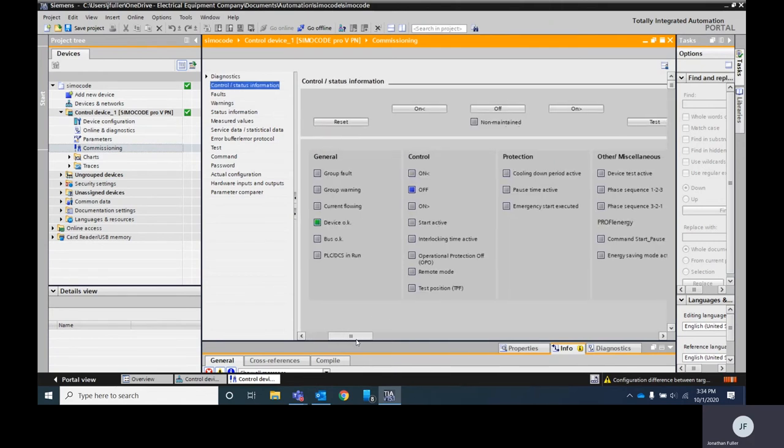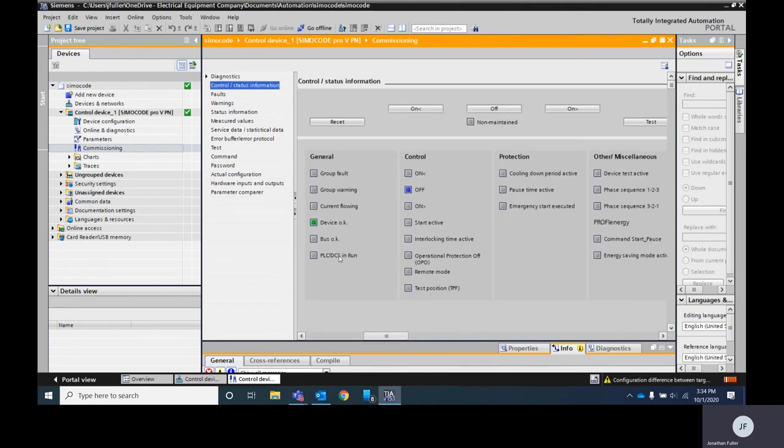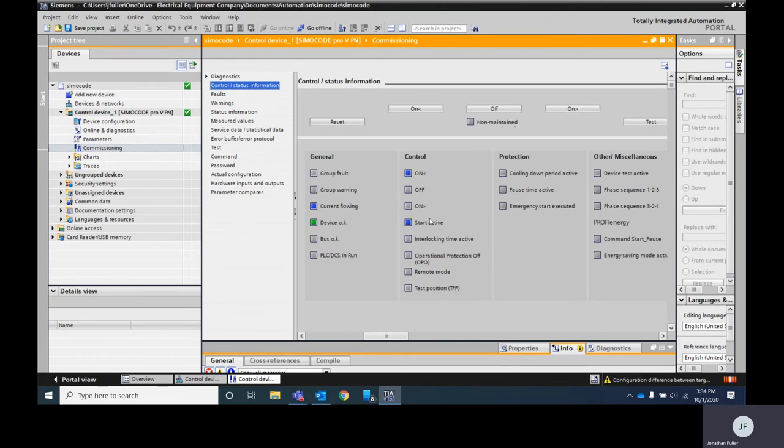You'll also see here I've got a general device OK off right now. If I were to hit a button on my demo stand start my motor spinning you'll see now I've got a current flowing, I'm on, I'm active. If I hit the other way you see I've got interlock active and then I'm now going again with the current flowing on and start active.